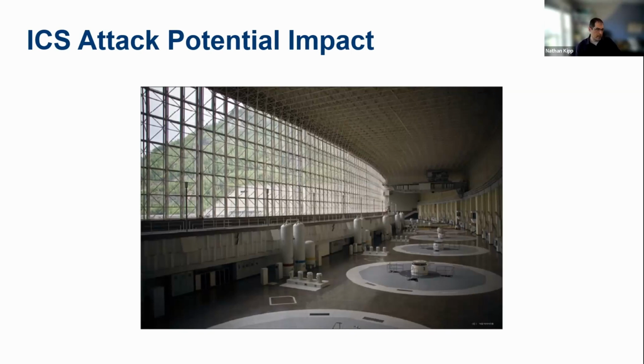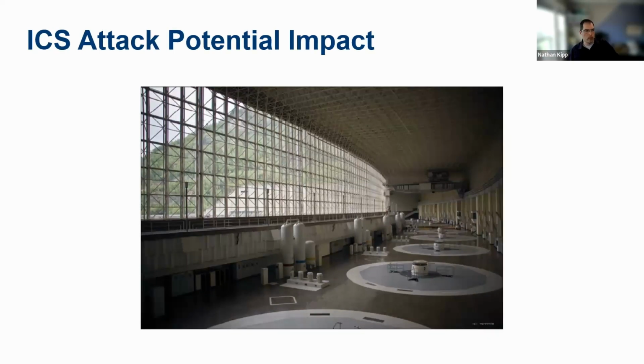What happened was an accident-type threat: the operator opened the inlet gate to the penstock, which lets water into the generator, starting it spinning and sending out power. Either it was the wrong gate clicked on the HMI, or he didn't realize this one was locked for maintenance. But from the control system, he did open the gate, letting a flood of water into the penstock.